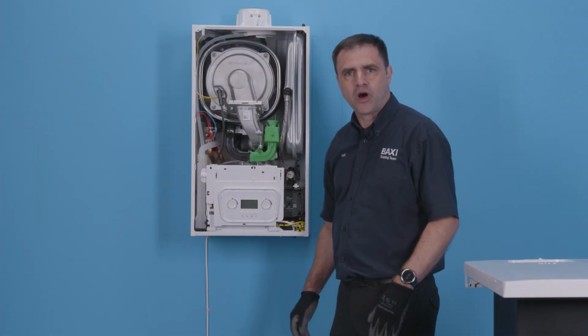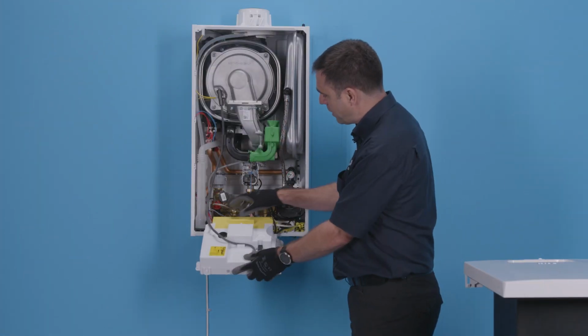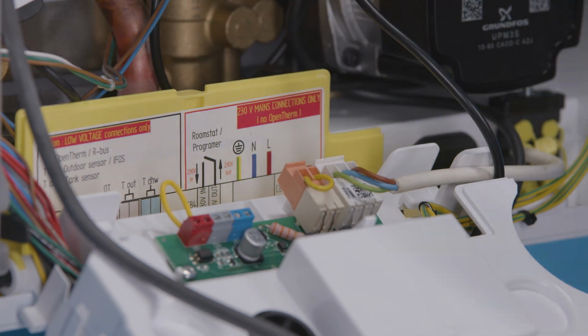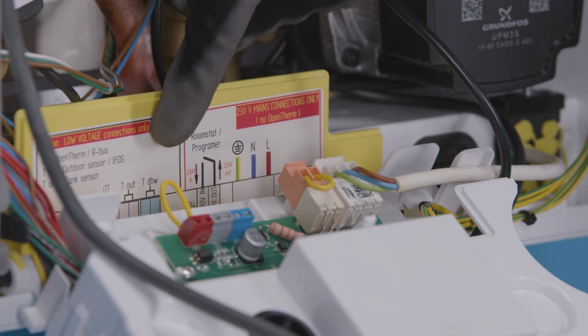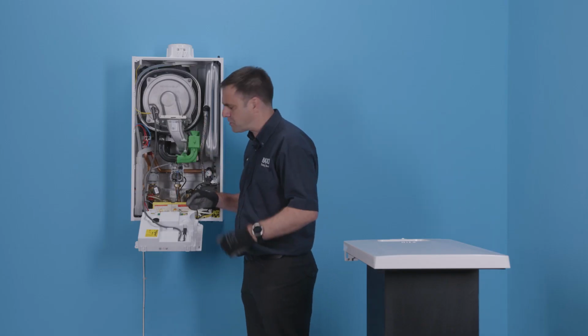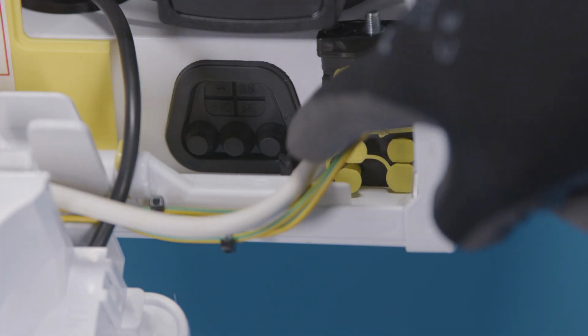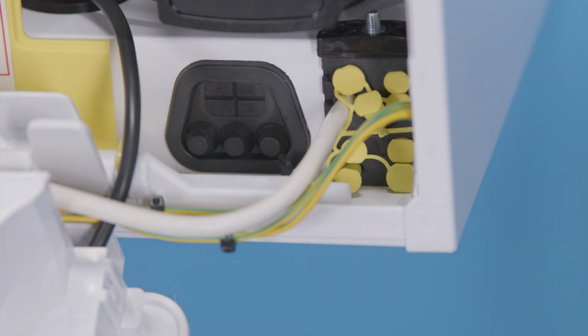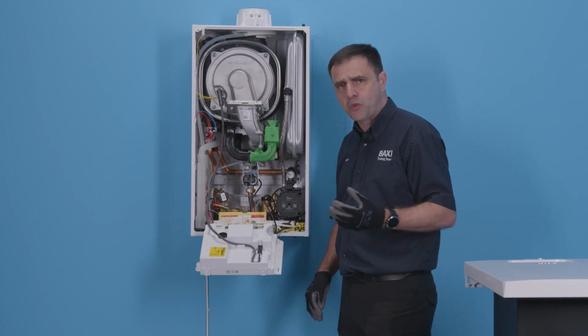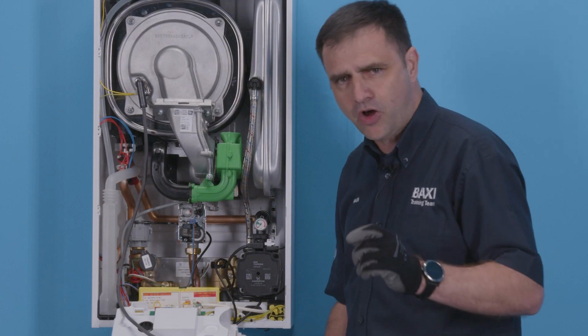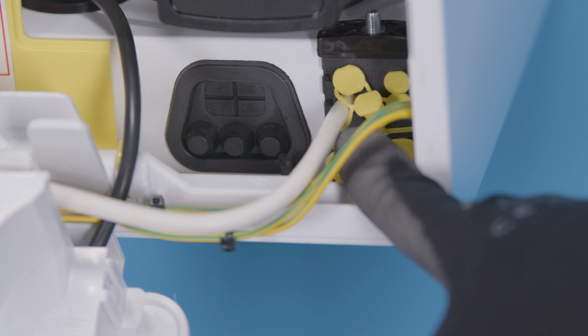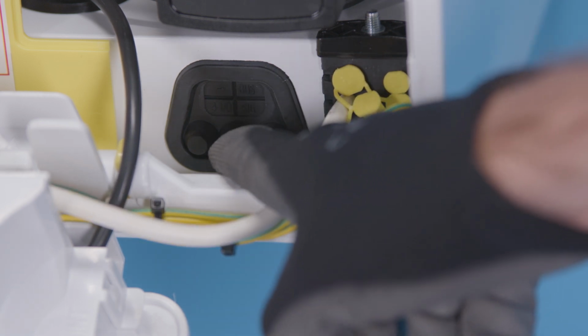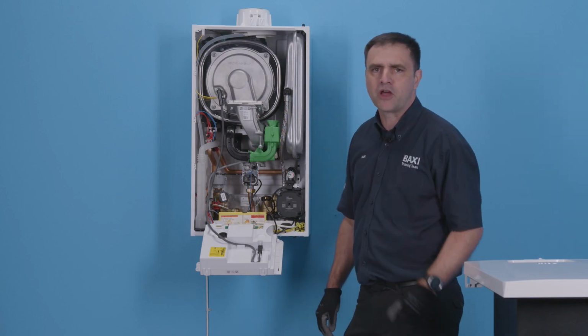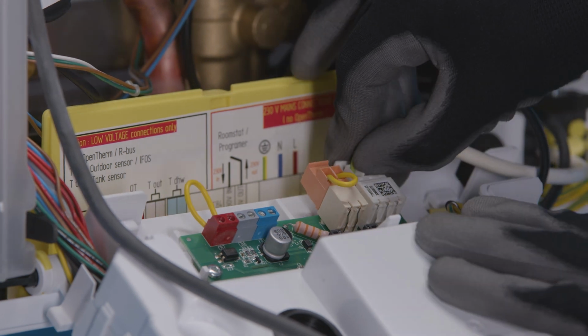Okay, so let's move on to the wiring. Drop the front panel down and we've got an easy access hatch here, with the wiring diagram, colour coordinated, making things very simple. As you can see, I've fed the wire through the correct size grommet. There's a range of options there. You select the right one for the wire that you're using. That's for the high voltage side. If you're using low voltage, you select one of these 3 grommets and you come through, separating the high and low voltage.